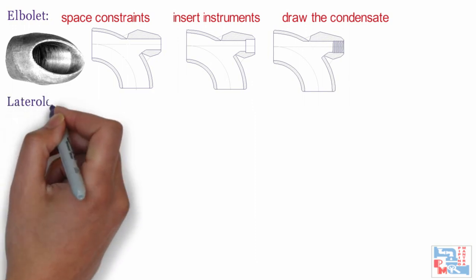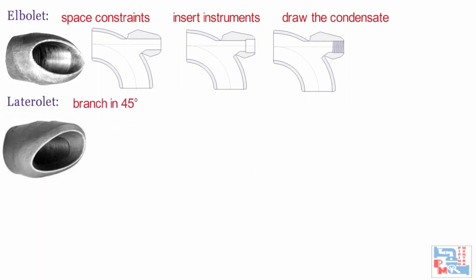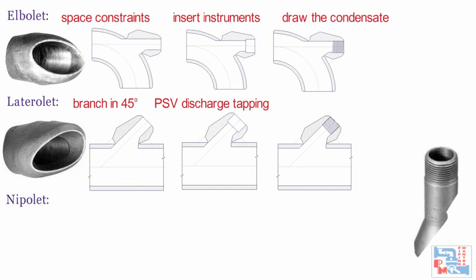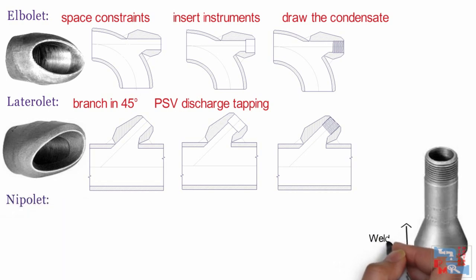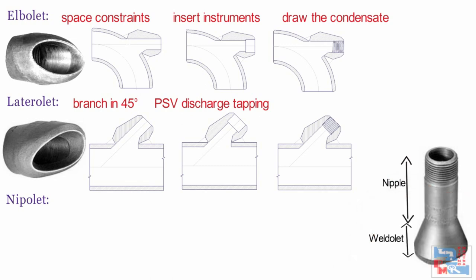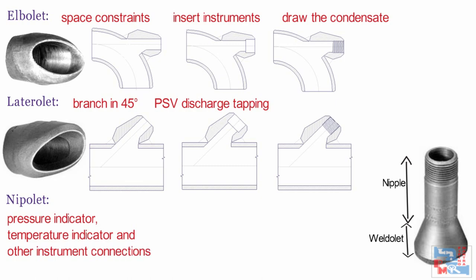Laterolet is used to have a 45-degree branch connection, as commonly seen in flare lines where PSV discharge tapping is connected at 45 degrees. It is also available in socket end and threaded end. Nippolet is similar to a threadolet but has a combination of weldolet and nipple with external thread — only fittings can be connected on the branch side, not pipes. It is used for pressure indicator, temperature indicator, and other instrument connections.